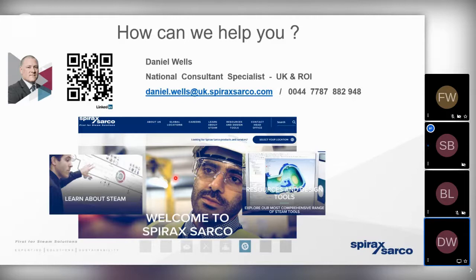Thank you very much. Just a couple more very quickly, if we may. So there's a question here from Ali, asking, can we install a plate heat exchanger horizontally when using steam as a heating medium? No. We need to allow for the condensate to be able to drain away correctly. So typically, not a plate heat exchanger.